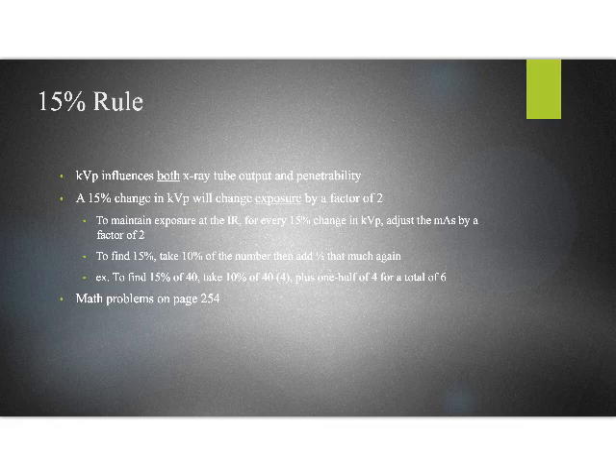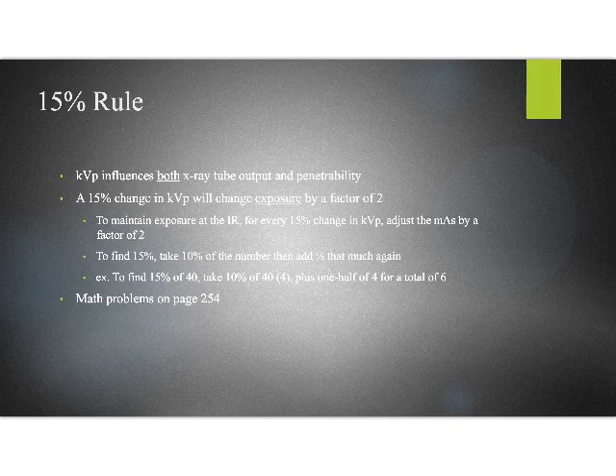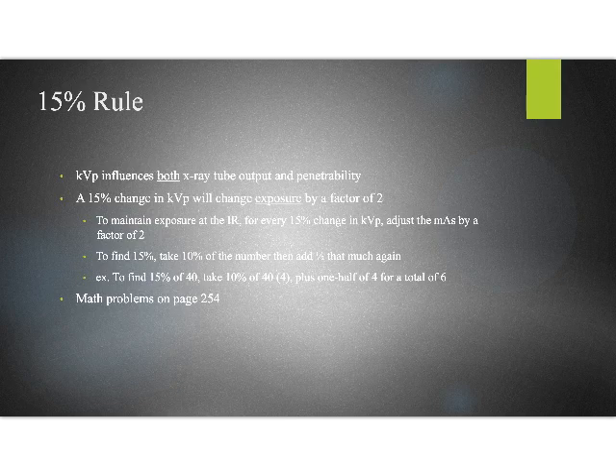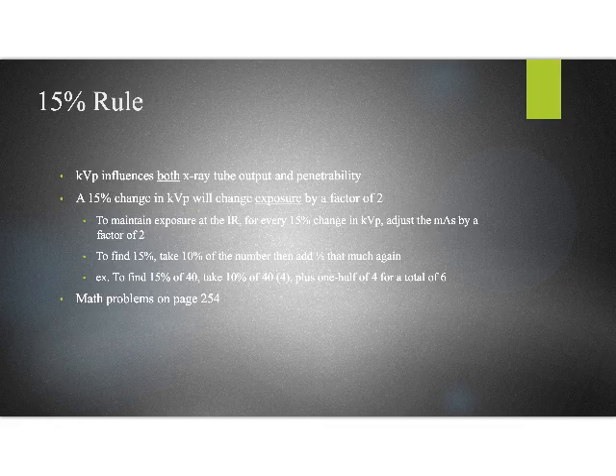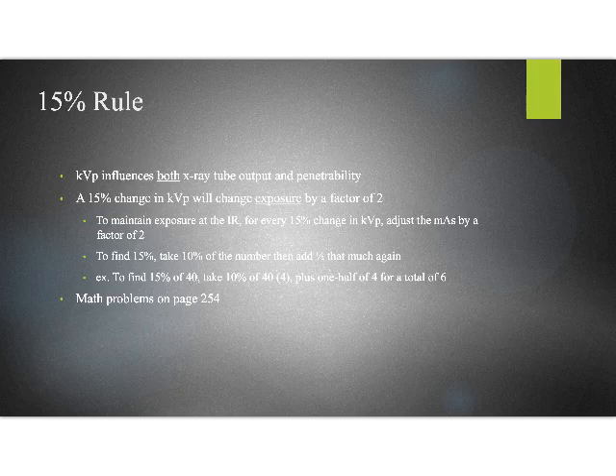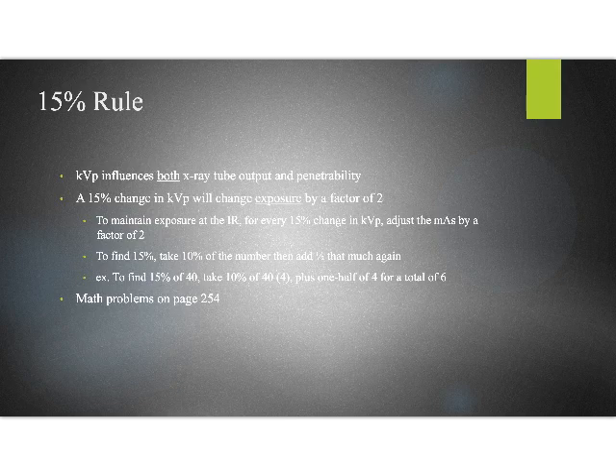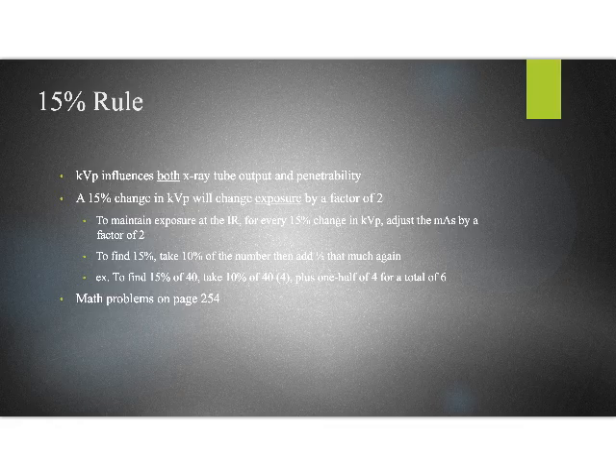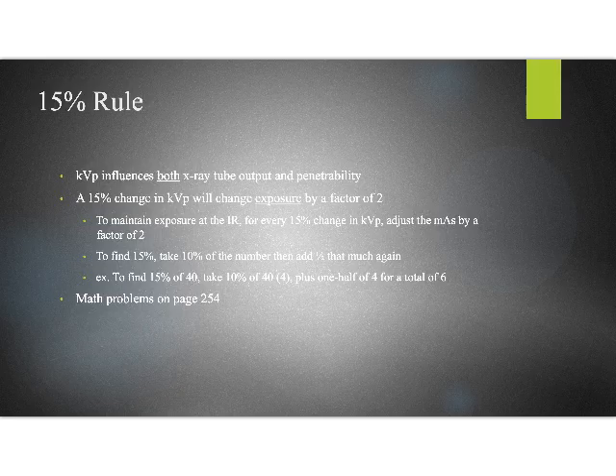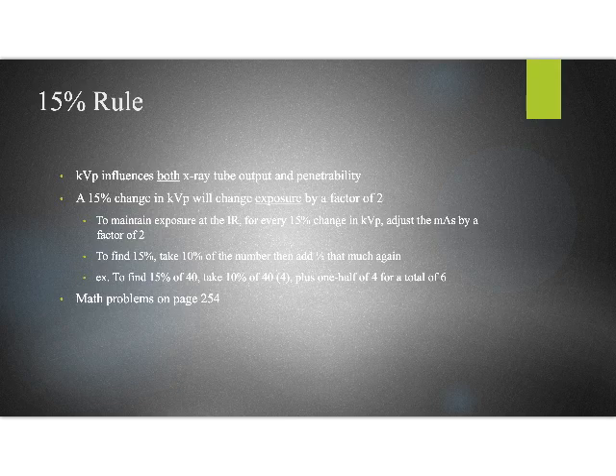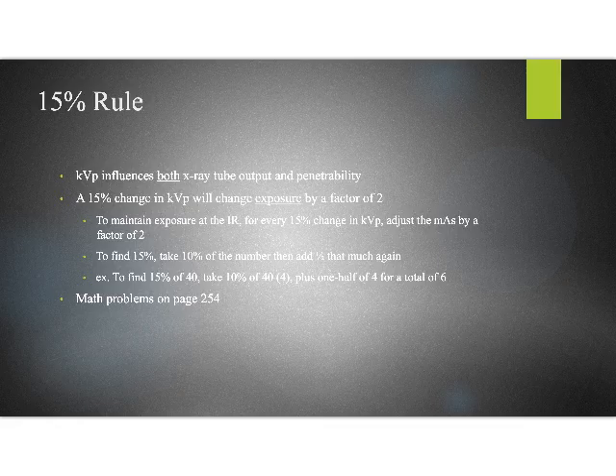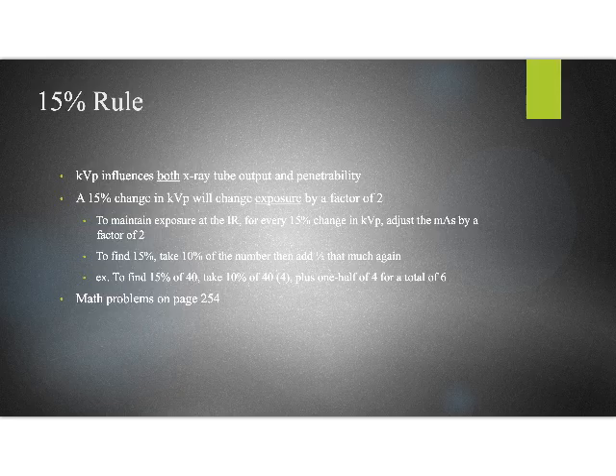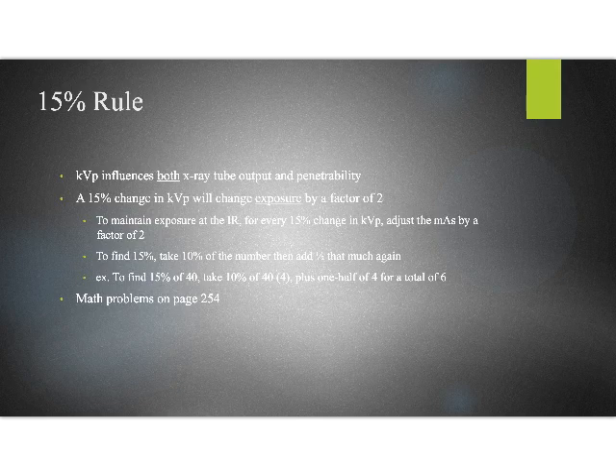The way that we talk about that is the 15 percent rule. He gives it in the oldest form right here, which is to maintain exposure at the IR, for every 15 percent change in KVP, adjust the mAs by a factor of two. I think that's the most concise way to express it. So if you want a quick way in your brain to find 15 percent, take 10 percent of the number. So 10 percent of 40 is 4. Divide 4 in half, that gives me 2. Add those together, it gives me 6. That gives me 6 is 15 percent of 40. That's just one example of maybe a quick and dirty way to do it. We will do some math problems though now so that we're all clear on this.